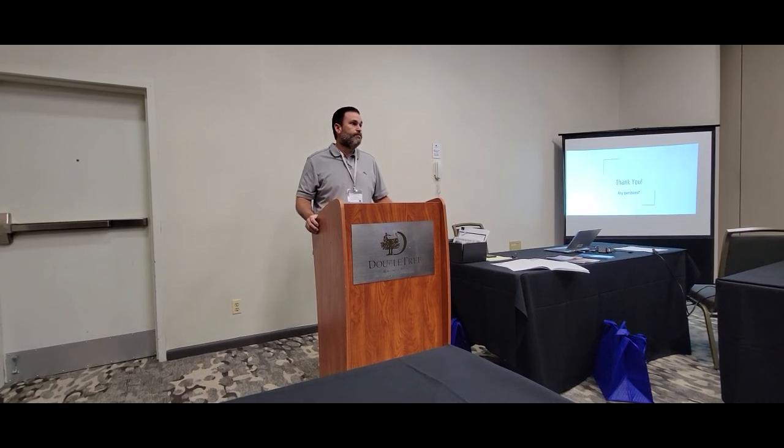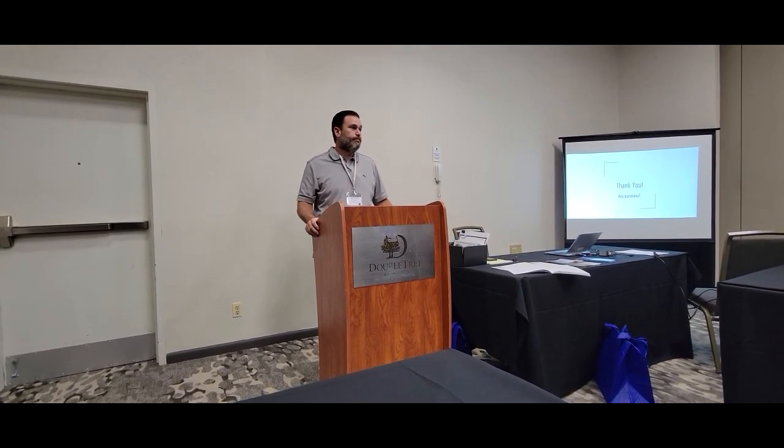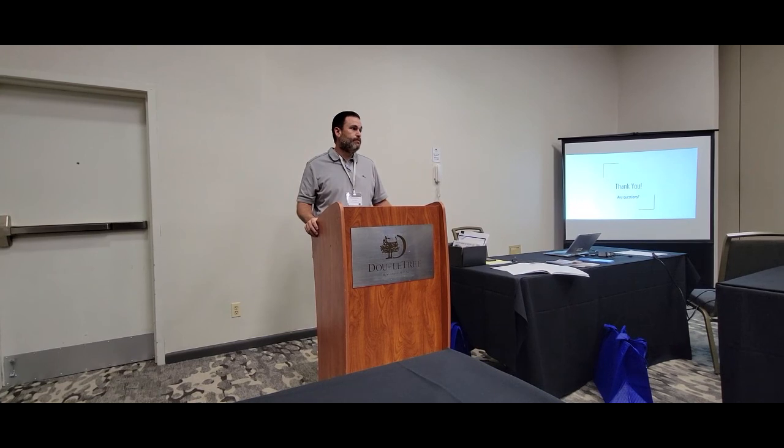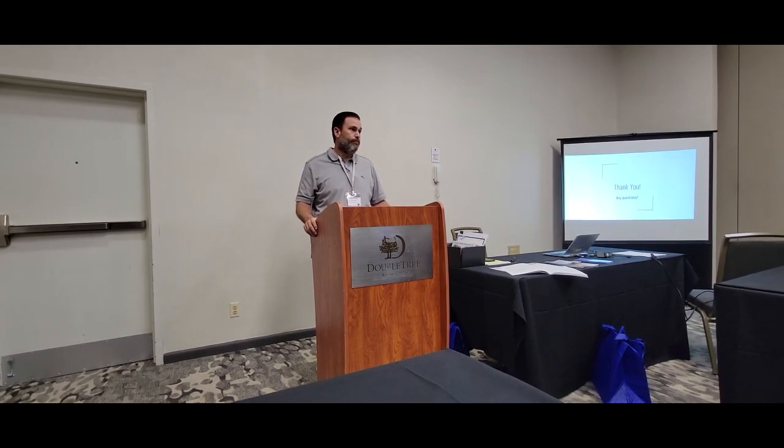and they're great. And even for rags, my experience is the volute style is going to do better. But every situation is different. You know, I'm sure with the Orange County Public Schools, you guys have had a lot of issues and went to the grinder and it worked great. Yeah, we did, especially on the small ones like the portable fields. If it's just a small little lift station or a portable field, they usually have just one little grinder pump. That we have.